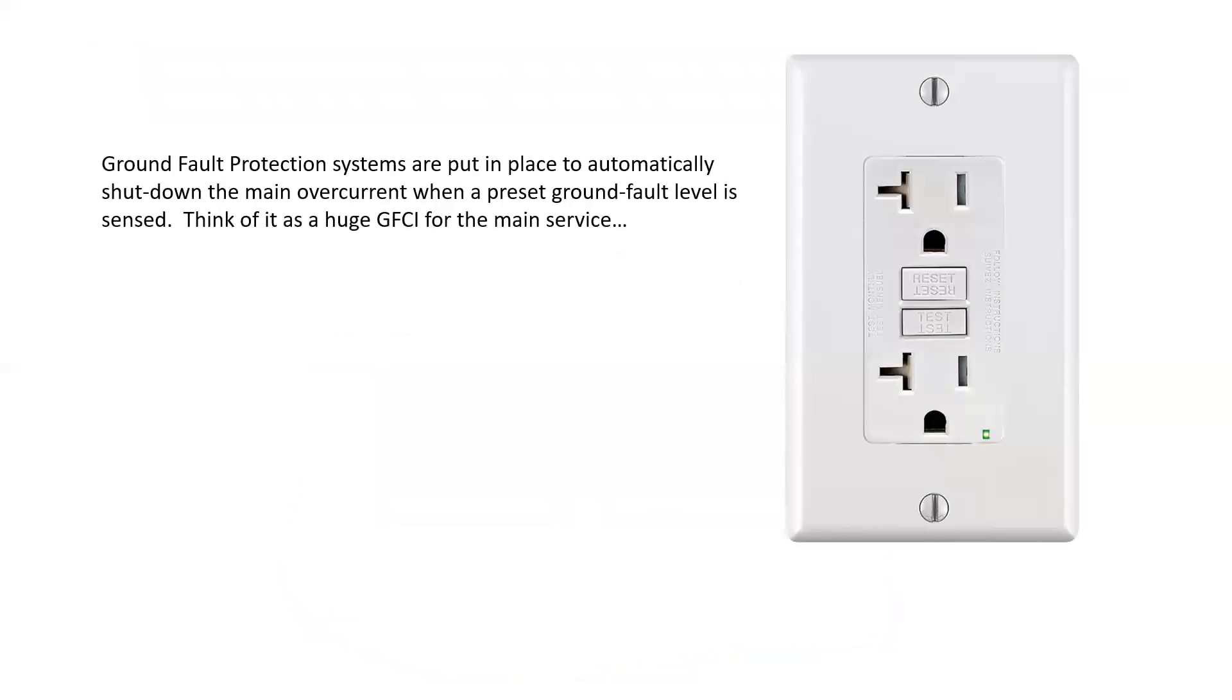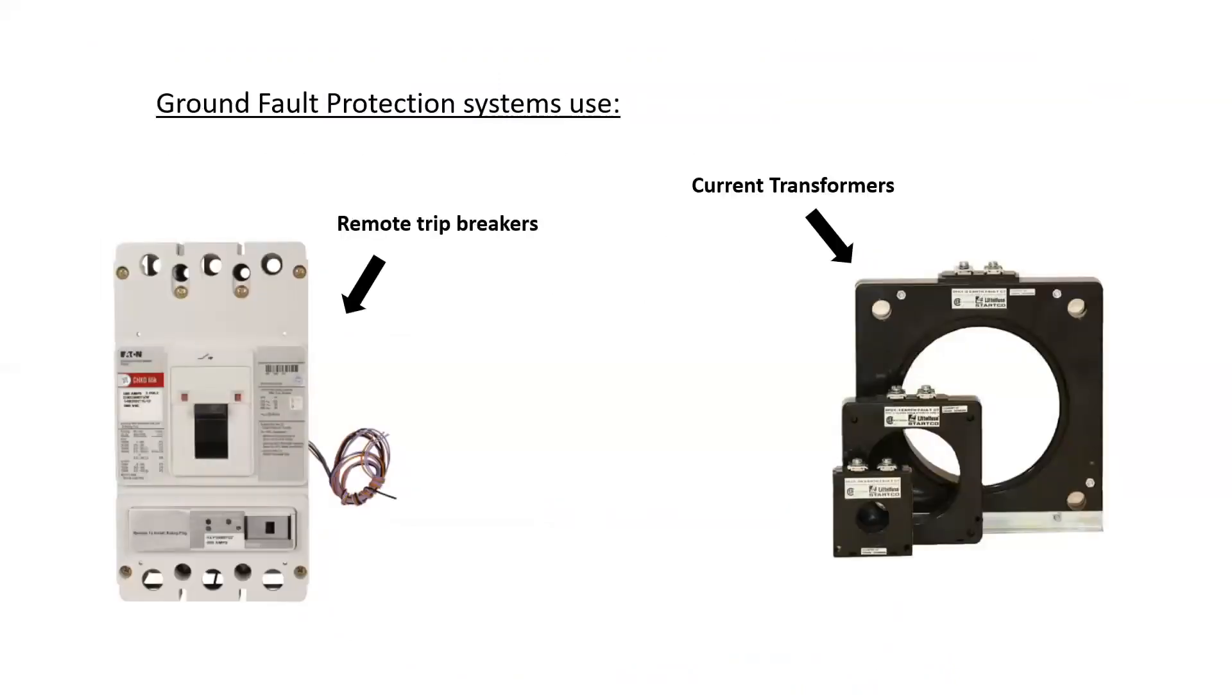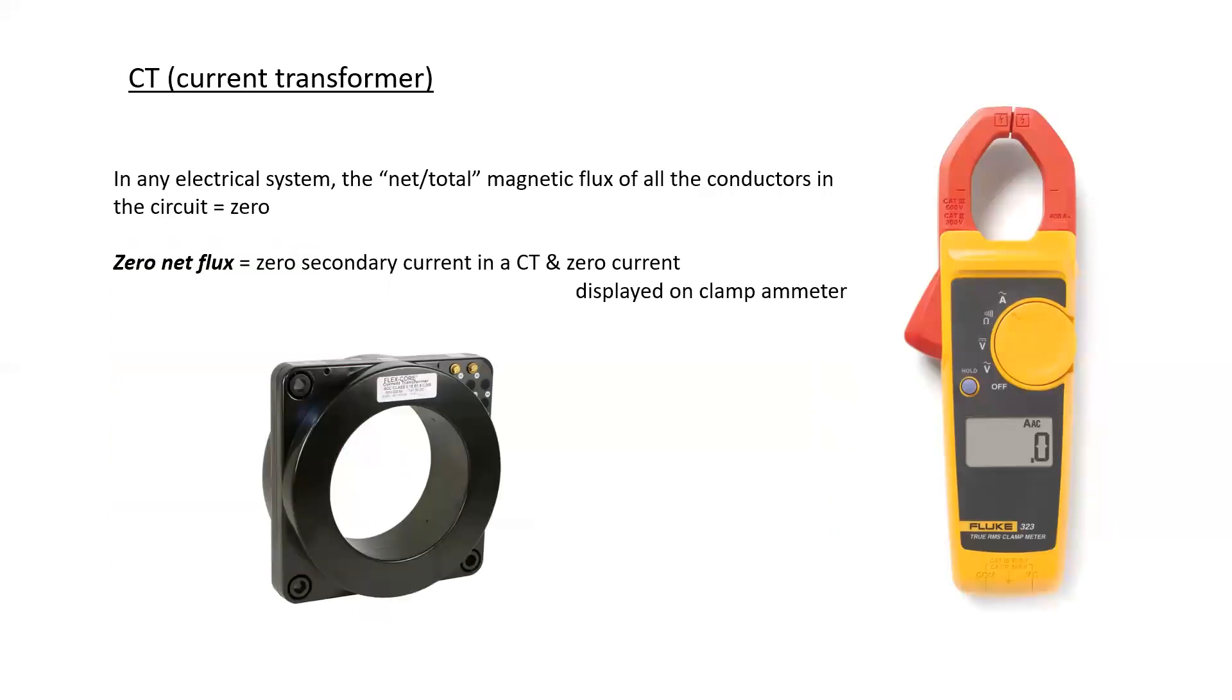Ground fault protection systems are put in place to automatically shut down the main overcurrent when a preset ground fault level is sensed. So think of it as a huge GFCI for the main service. Ground fault protection systems use remotely tripped breakers and current transformers or CTs. Often, the two items are built together in one unit.